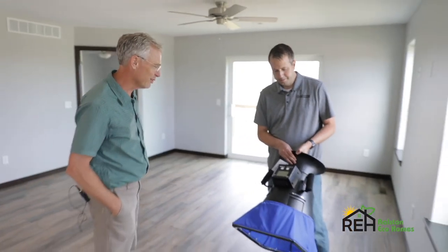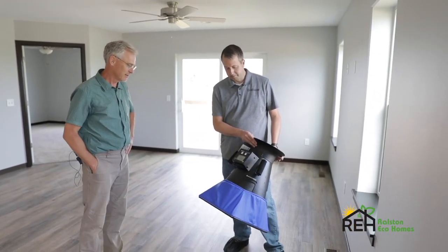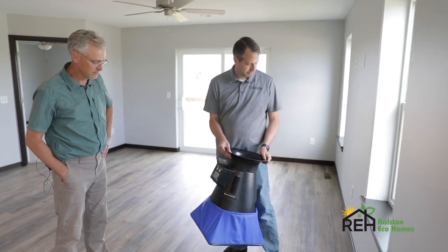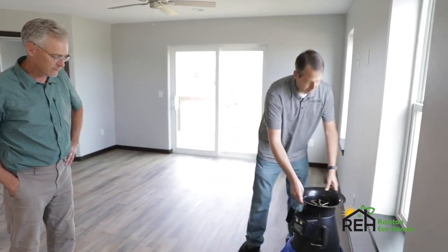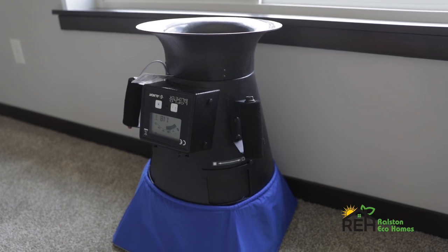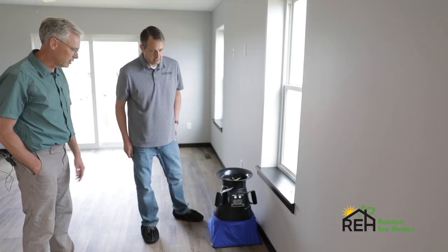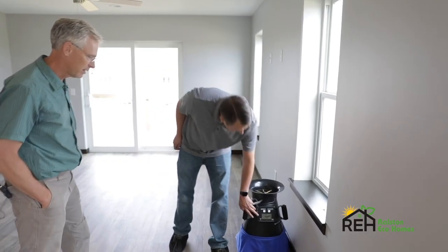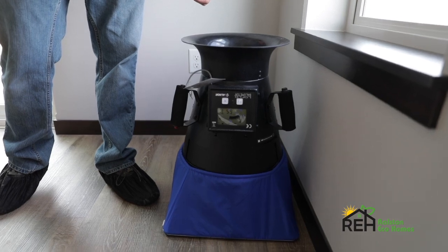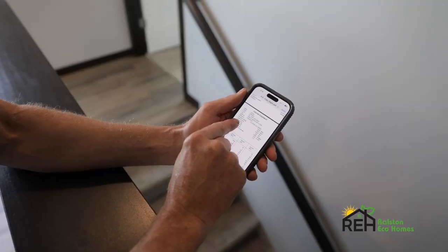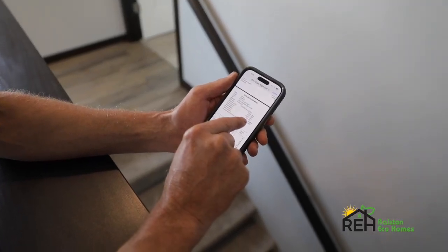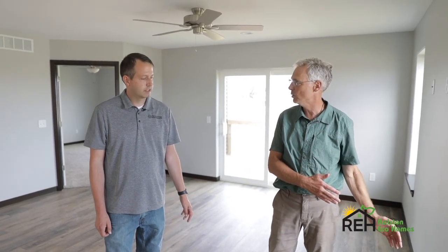Yep. And what do you have here? This is kind of funky. This is a flow hood, measures the air coming out of the vents. So we'll see what we've got. So that just sits over the register or the duct, and then it's going to measure the flow coming out of that. So we're going to be able to see the flow, and it looks like we're getting about 86 CFM. As part of designing this system, we would have given a value to each register. So this register would have been designed to provide a certain amount of flow.